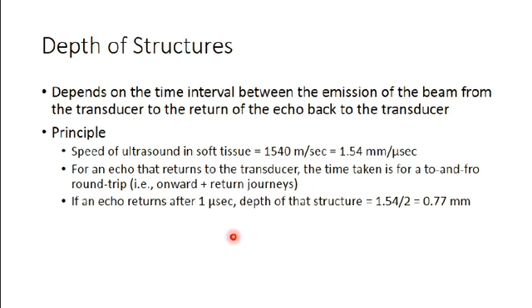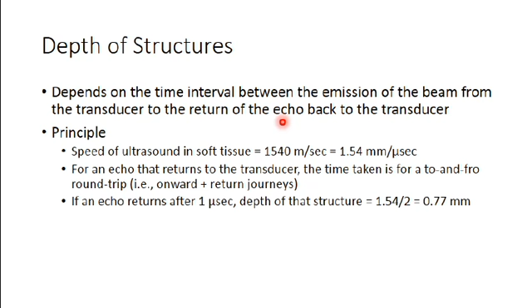Okay, I repeat, the ultrasound beam takes about 1 microsecond to travel 1.5 millimeters. Because it's a round trip both onward and return, you'll have to divide the time by 2 to get the distance of the structure from the probe. So if an echo comes back after 1 microsecond, so the echo returns to the transducer after 1 microsecond, it means that that structure was about 0.77 millimeters from the probe. So it goes, hits the structure, so that takes about 0.77 millimeters, and then comes back another 0.77 millimeters, and that's 1.54 millimeters, and 1.54 millimeters takes about 1 microsecond. This is how the computer determines the depth. Okay, it just takes into account this fixed relationship of the speed of sound in soft tissue.